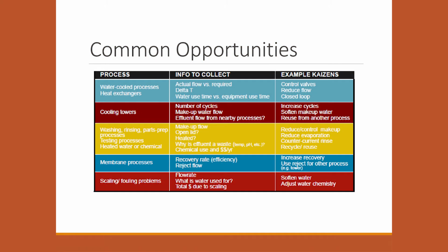So here are some common opportunities at manufacturing sites especially to save water and in the process save energy. I won't go through all of them, but we can touch on cooling towers here. One of the things we talk about is the number of cycles. Sometimes cooling towers are set up so that they always blow down after the same number of cycles, but during a water Kaizen Blitz event, we can go in and test the water to see if it's actually needing blowdown at the point where we're doing blowdown. There's a chance that we're blowing down when that water is still fine for a few more cycles, so we can increase the number of cycles.